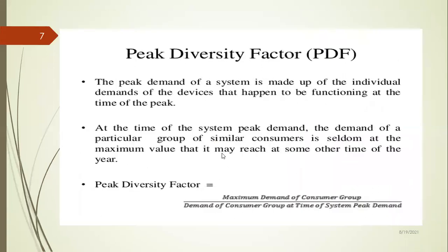Now the next one is the peak diversity factor. Okay, now what is the peak diversity factor, PDF? The peak demand of a system is made up of the individual demands of the devices that happen to be functioning at the time of peak, at the time of system peak. So at the time of system peak demand, the demand of a particular group of similar consumers is seldom at the maximum value that it may reach at some other time of the year.